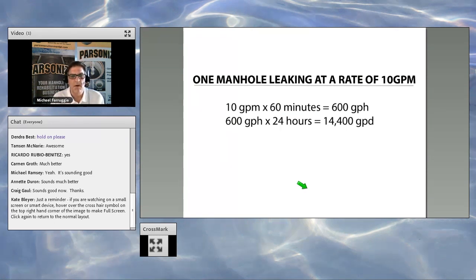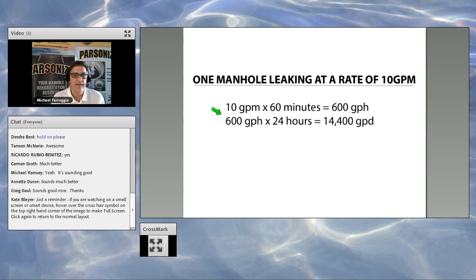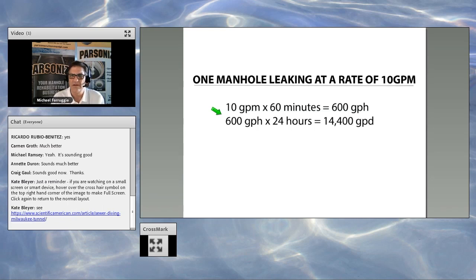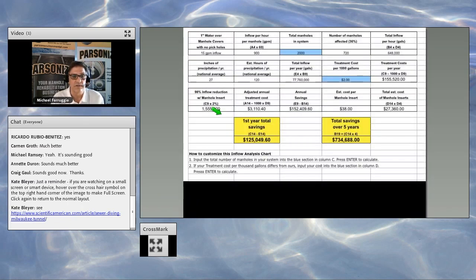This slide about one leaking manhole — the first time I heard these numbers, it blew my mind. If you think of one manhole in your system that leaks 10 gallons a minute, over 60 minutes that's 600 gallons. Over a 24-hour period, you're talking 14,000 plus gallons. If a sewer treatment plant is paying somewhere around $1.75 to $2 per thousand gallons to treat that water, you're talking about spending somewhere around $9,000 per year to treat water that was clear — it didn't need to be treated. Recently in Milwaukee, they spent $3 billion doing detention for inflow and infiltration for their storm drains, with one tunnel costing around $162 million. You can see there are big numbers in controlling this, and good reasons to do so.